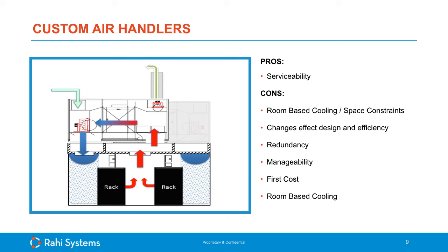So on the next slide, custom air handlers, also very widely used, are typically placed outside, either on the rooftop or next to the data center. In this case, you see one sitting up on the roof, pulling the hot air from the hot aisle. Here it's using a containment system, dumping the air into the cold aisle. They're again very easy to maintain and service. They're built to move a great deal of air as efficiently as possible. But this also makes them quite large, and they have similar space constraints and redundancy issues once designed in. They can be designed in modular chunks, which can actually help mitigate the cost of construction. However, they also tend to have higher first costs compared to the other systems.